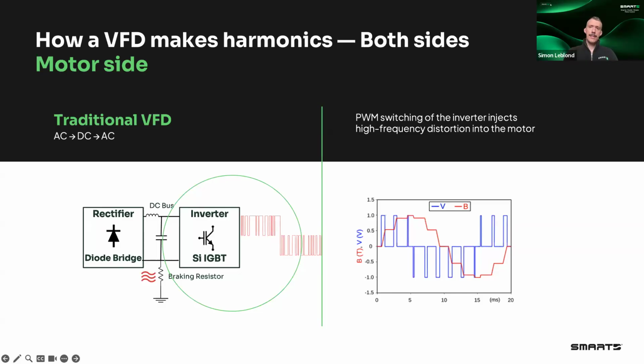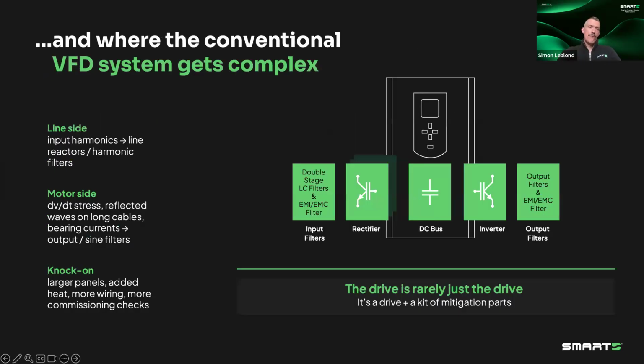But really, here you've got one phenomenon on the grid and one on the motor side, and both get addressed through mitigation. You're adding band-aids to that problem through filters on the grid and filters on the motor side, expanding the size of your panel, adding potential heat losses. So it's really a drive plus a kit of external parts, very often put into a panel. For one drive, one install, it's manageable. When you have 30 to 50 to manage in your data center, it becomes a compounding problem, really.